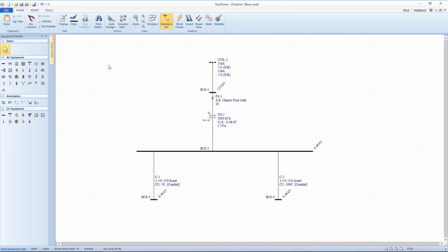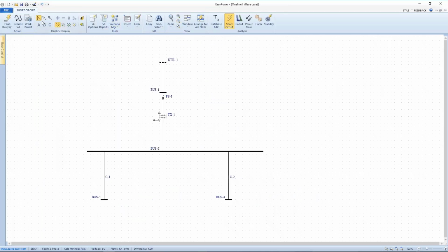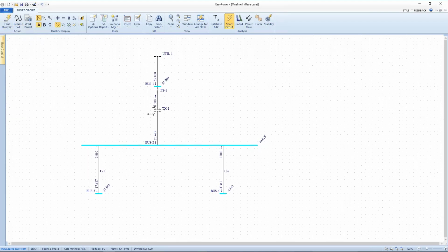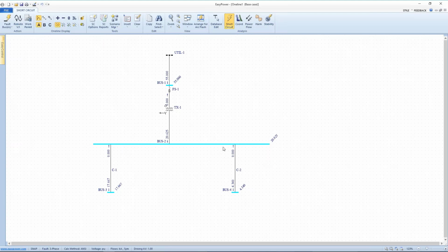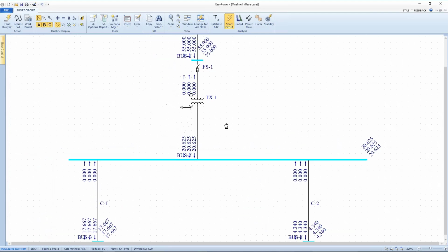and apply. So now that I go to short circuit focus, we're going to be looking at a half cycle balanced three-phase fault. So here at the top, I'm showing a half cycle fault, and it's balanced three-phase, and we're going to fault all the buses. Now at this point, what the tool is showing me is the fault current at each of these buses. Now, we're looking at just the A phase. If I wanted to, I could look at all three phases, and that's all well and good, except with a balanced fault that's redundant. So we're just going to look at the A phase for now.